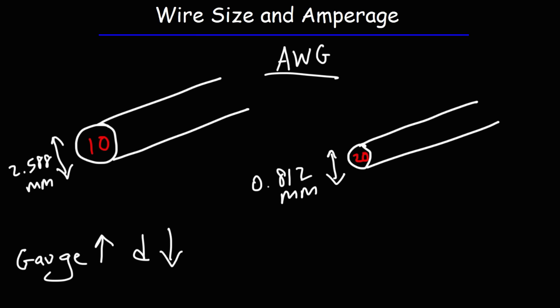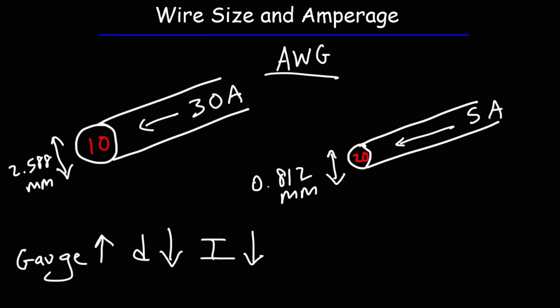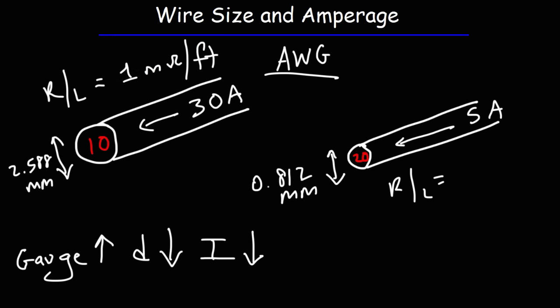A wire gauge of 10 can handle a current of 30 amps, whereas a wire with a gauge of 20 can handle a current of 5 amps. So as the gauge number increases, the amount of current it can handle decreases. The resistance per unit length of a wire with a gauge of 10 is 1 milliohm per foot, whereas for a gauge of 20 it is 10 milliohms per foot. So as the wire gauge increases, the resistance per unit length increases as well.